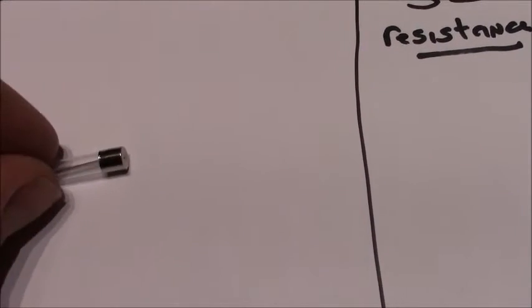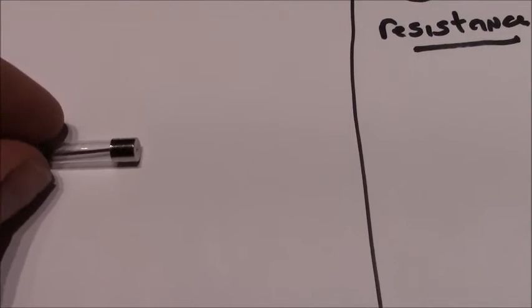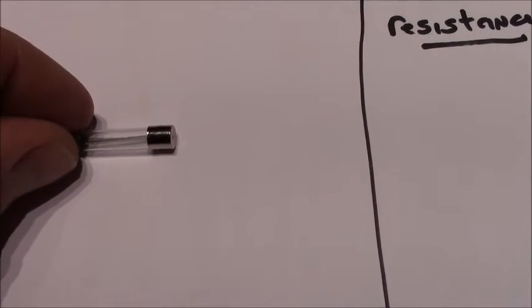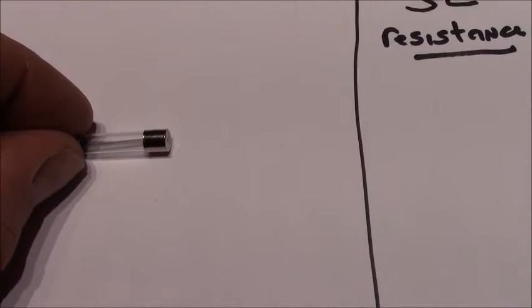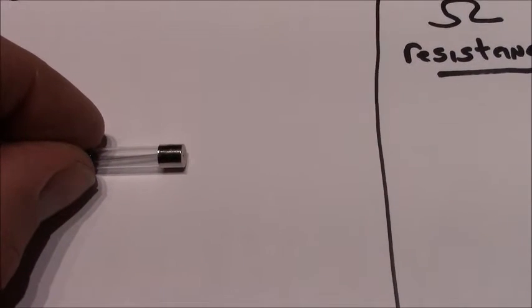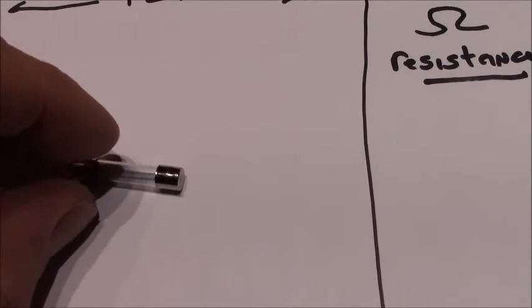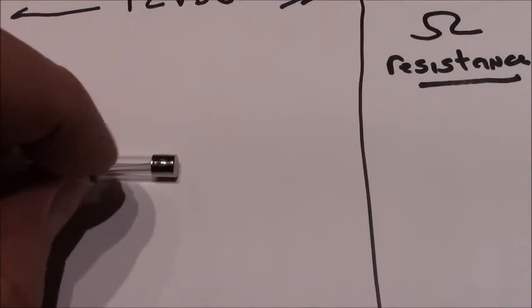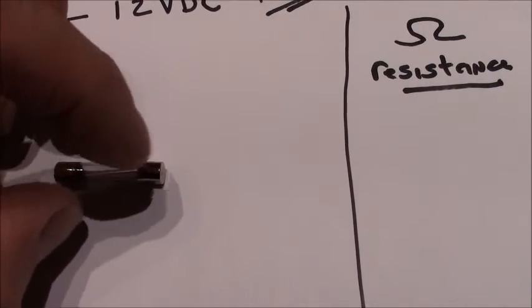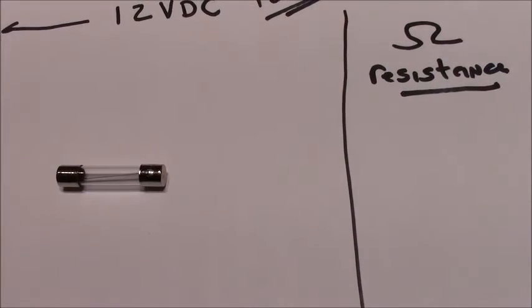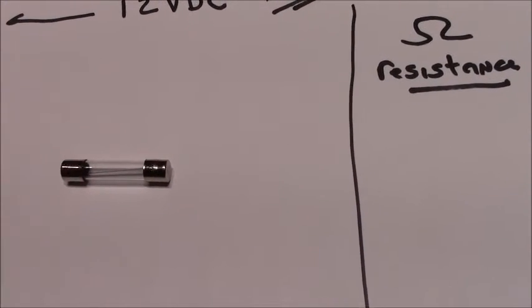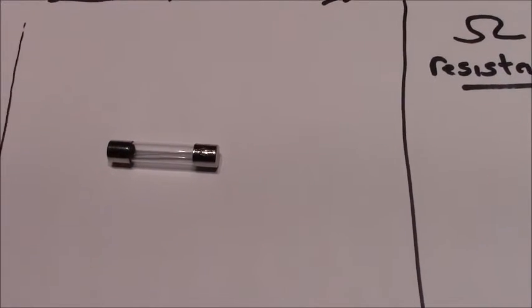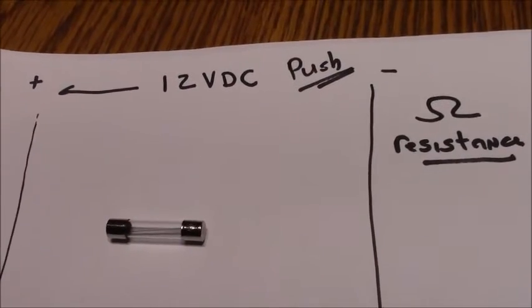The filament here is still in excellent shape, nice and shiny, and you can see it runs from one end of the fuse to the other. If this fuse had burnt, you'd see some blackish discoloration, and the fusible link inside would have separated. It would have melted to a degree.